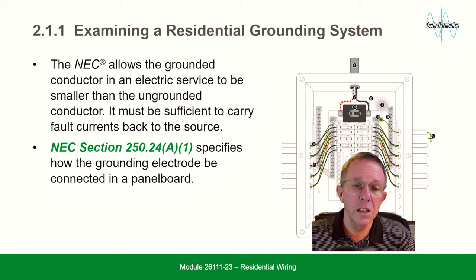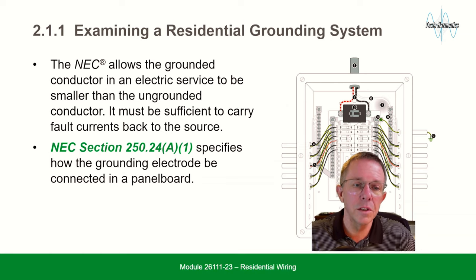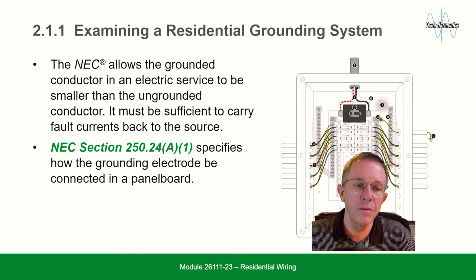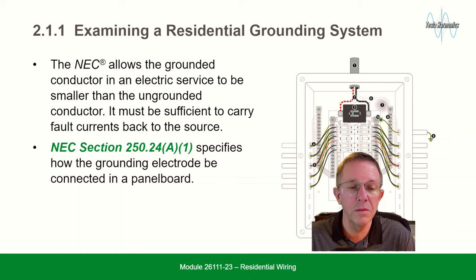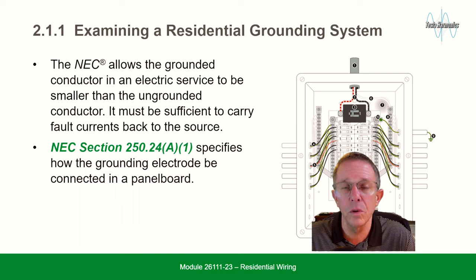Examining a residential grounding system: the NEC allows the grounded conductor at the electric service to be smaller than the ungrounded conductor. It must be sufficient to carry the fault current back to the source. NEC section 250.24 specifies how the grounding electrode must be connected in a panelboard.